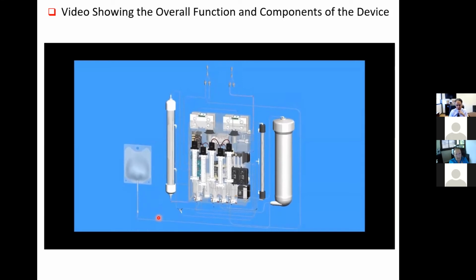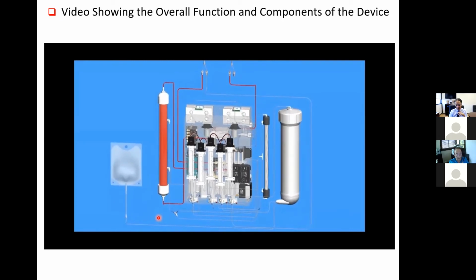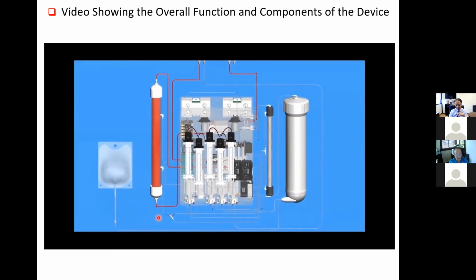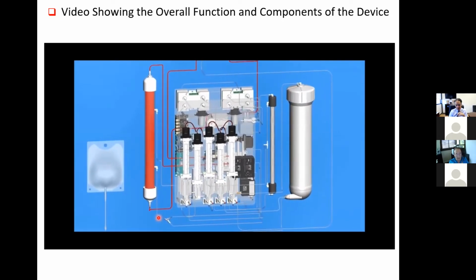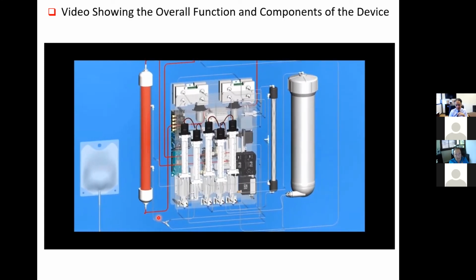The purifying process begins with blood flowing from the patient through a catheter, as shown in red on the top right. It then flows to a peristaltic pump and enters the ultrafiltration module, which is shown as a cylinder on the far left. This module retains proteins, white blood cells, and red blood cells to be returned to the patient's bloodstream through a separate catheter, as shown by the red stream returning out of the top left. Our system uses a unique nanocellulose membrane, which allows for minimum fouling as well as a high flow rate.